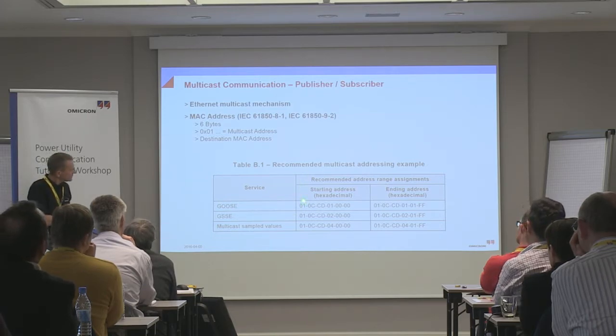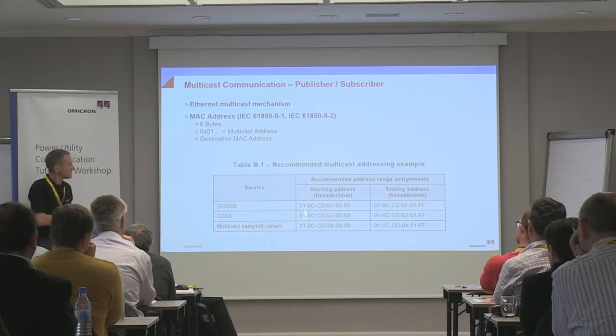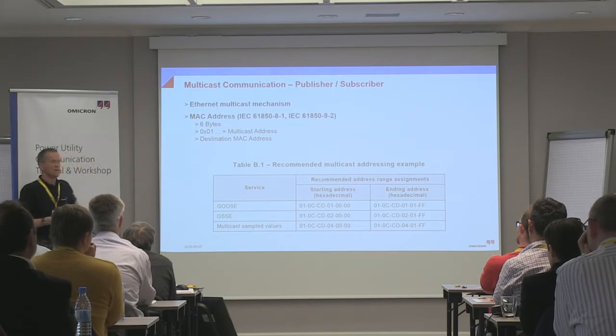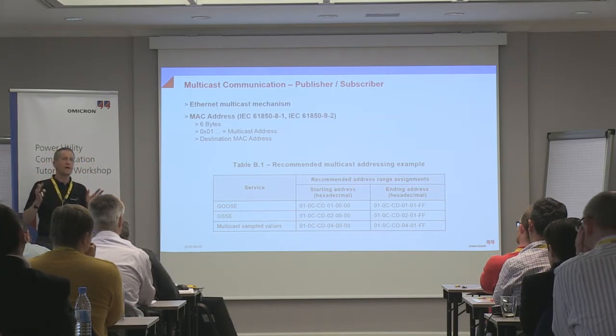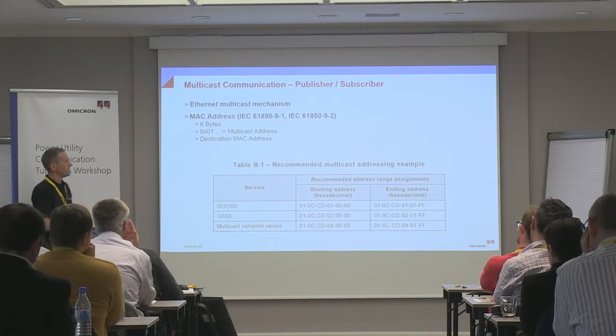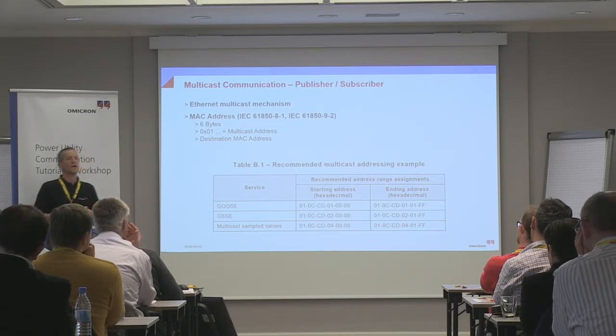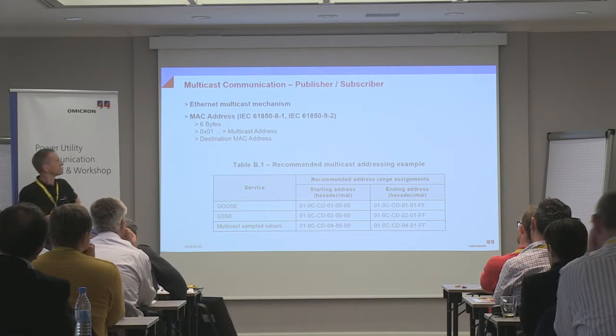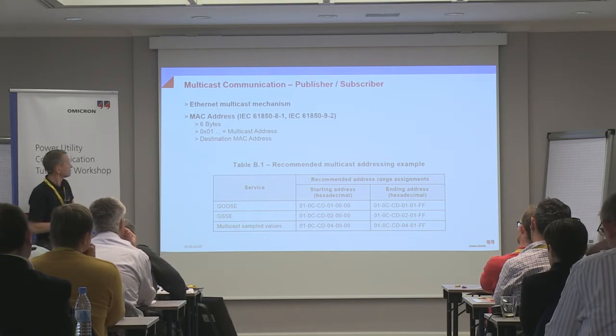By the way, this one here, this is the multicast bit. As soon as this bit is set, the packet is a multicast packet. So it makes sense to think about putting GOOSEs into the same multicast address group. If you want to do multicast address filtering, this is very much beneficial later on.